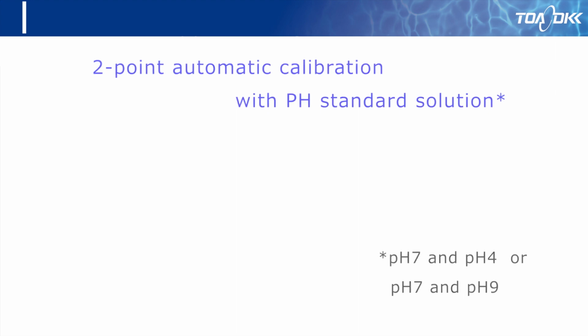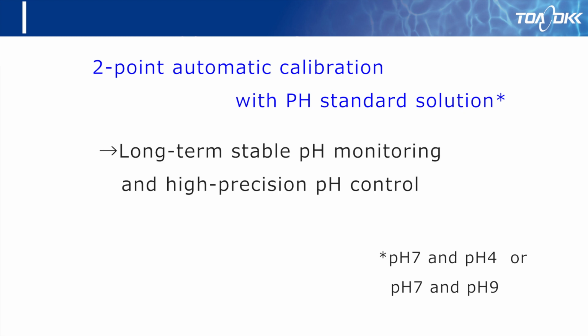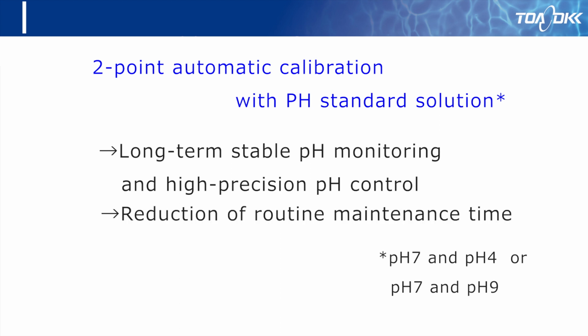First, we will introduce the features of MAC-1600 and where it should be used. One of the distinctive features of this product is an automatic calibration function. It automatically and accurately performs 2-point calibration using pH standard solutions. This enables long-term stable pH monitoring and improving the accuracy of pH control. You can reduce routine maintenance time.